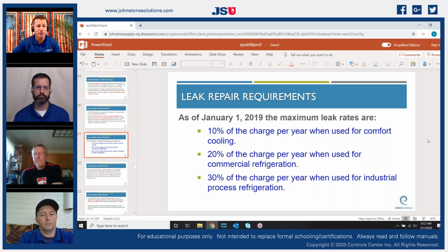As we progress into these type 2 and type 3, we're just following this lineage and we're getting set up for that next level. So if you're working in an air conditioning environment, you could have refrigeration systems in that same building, right? So what they're saying is if you encounter a refrigeration system, you are allowed to have a 20% leak rate on it. So if it was a 10-pound system, if it leaked 2 pounds of refrigerant, we are required to go find that leak. It's not just that we can go to the home or go to the business owner and go, hey, you've got a leak, I'm going to add 2 pounds of refrigerant. Now you're going to be required by law that if it has leaked those 2 pounds on that refrigeration system, you as a technician are required to at least fix that leak or inform that owner that they have met a federal regulation on their leak rate and they are required to have this repaired. It has to be documented.